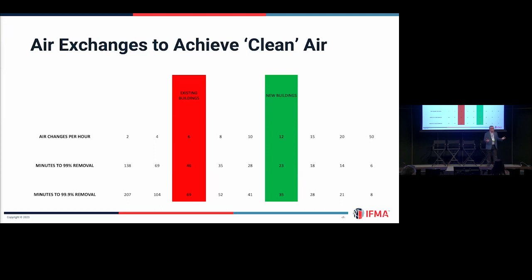Sometimes you have to bring in something temporarily to take the odor out of the air. You might have to bring in some activated carbon filtration system just so people can breathe. I know we've gone back to normal economizer mode now. We're no longer doing 100% outside air. We think COVID's gone to that point. So that will help come fire season if we have fires again. But even then, you're still going to be bringing in some outside air because you're right. You can't shut down your outside air. People can't breathe in that kind of a stuffy environment.